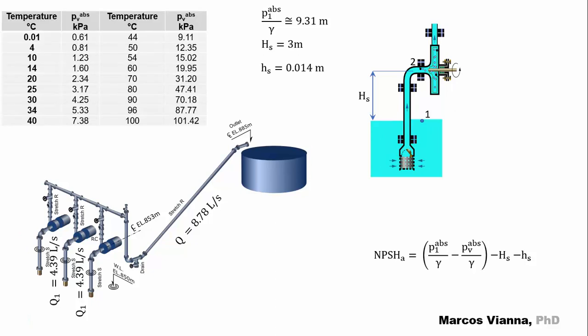The absolute head, corresponding to the vapor pressure, can be found in tables like this. Assuming that the water temperature is 20 degrees Celsius, we find the absolute vapor pressure, which can be transformed into the head that we need. Now we've got everything we need. We substitute the values and here it is, the available NPSH.